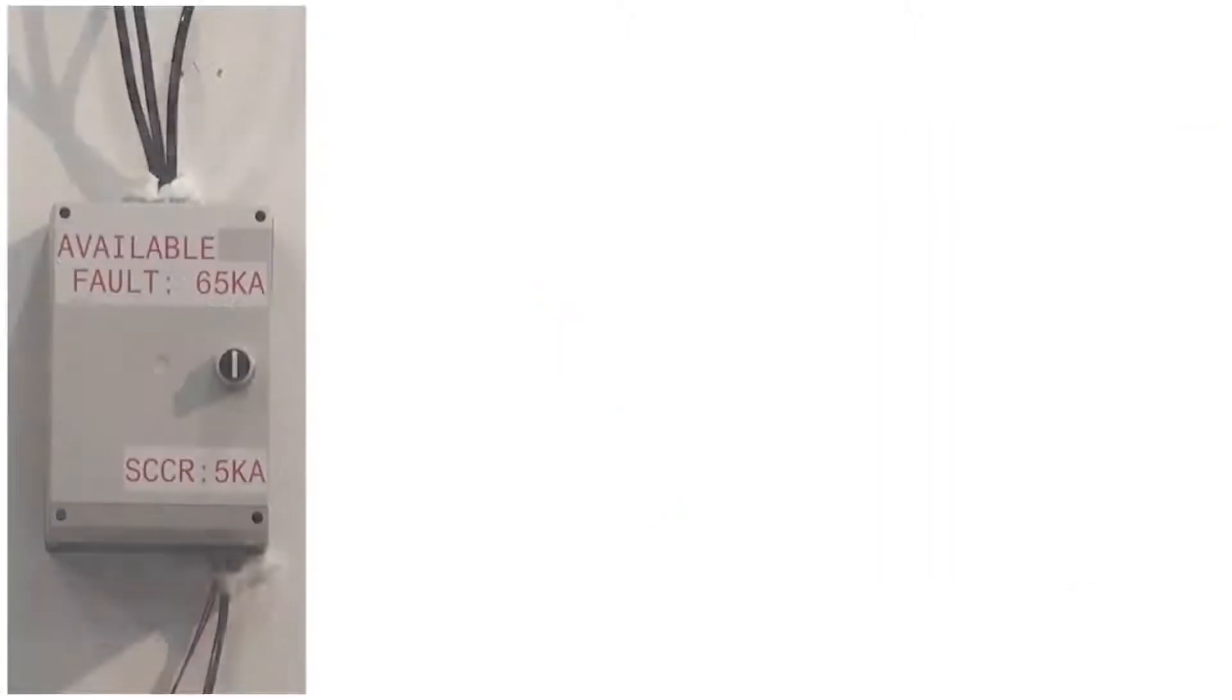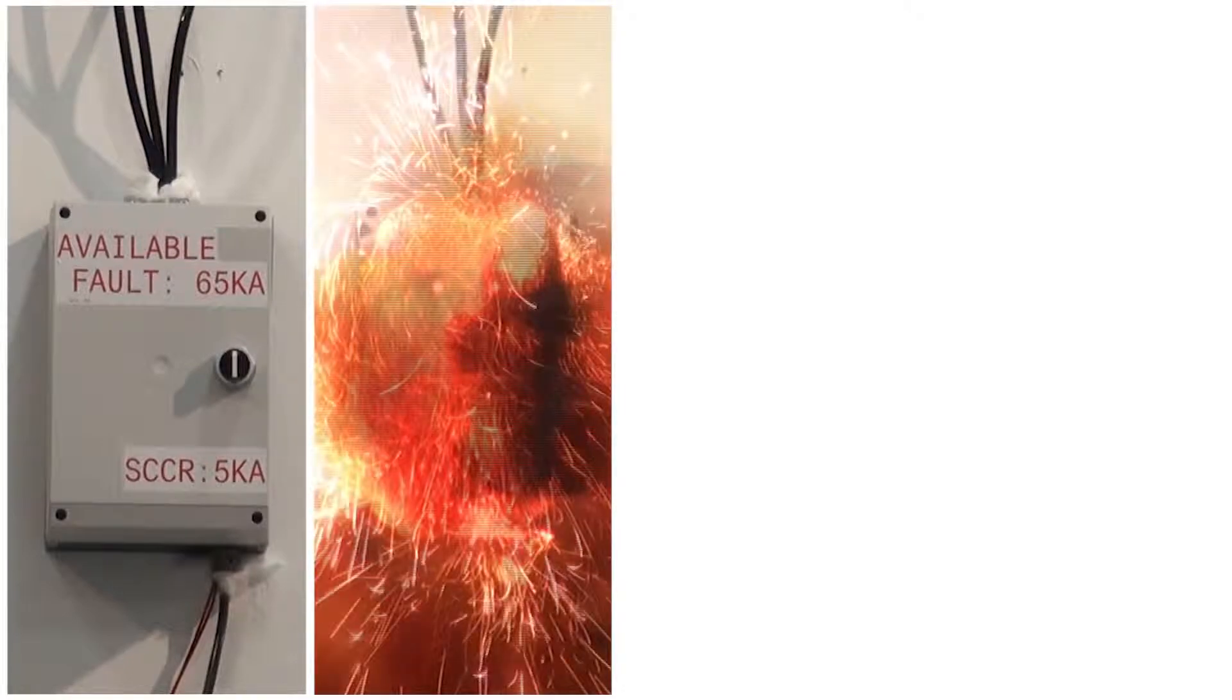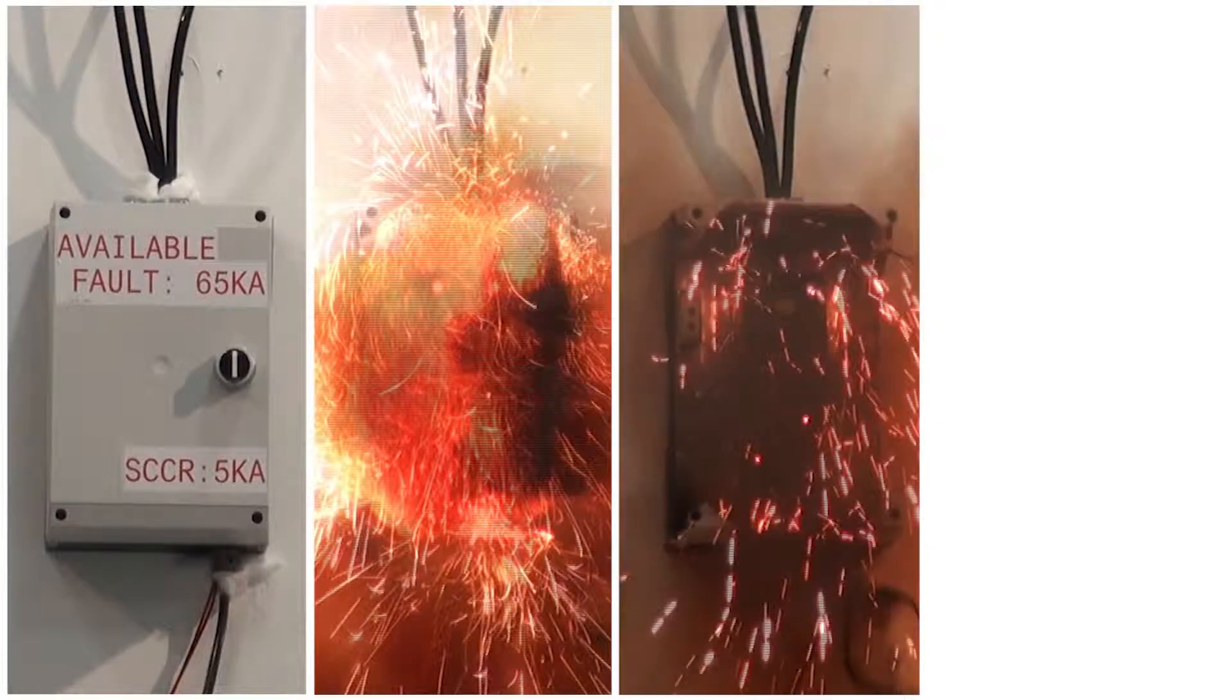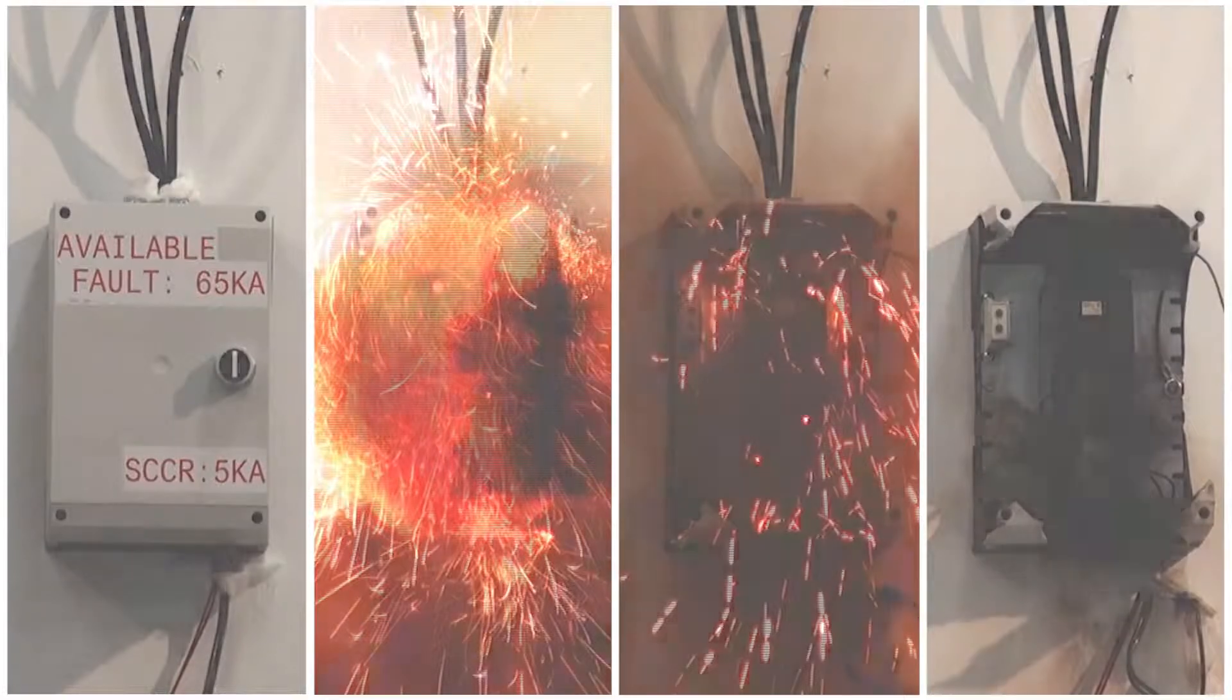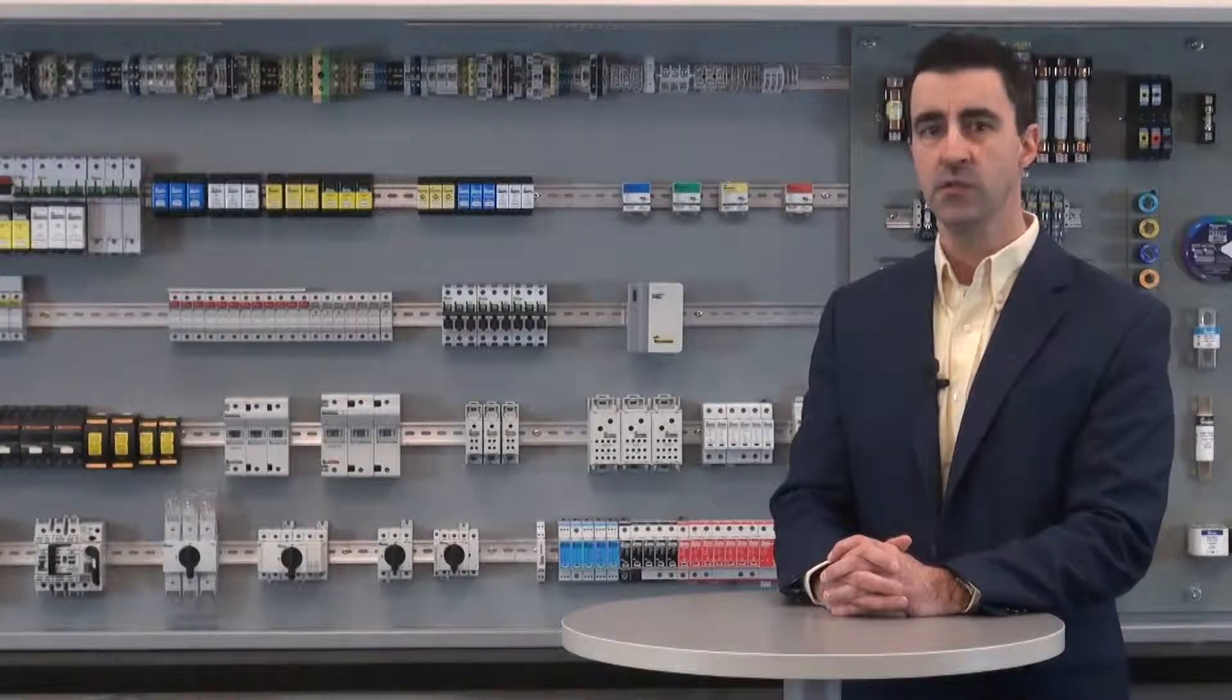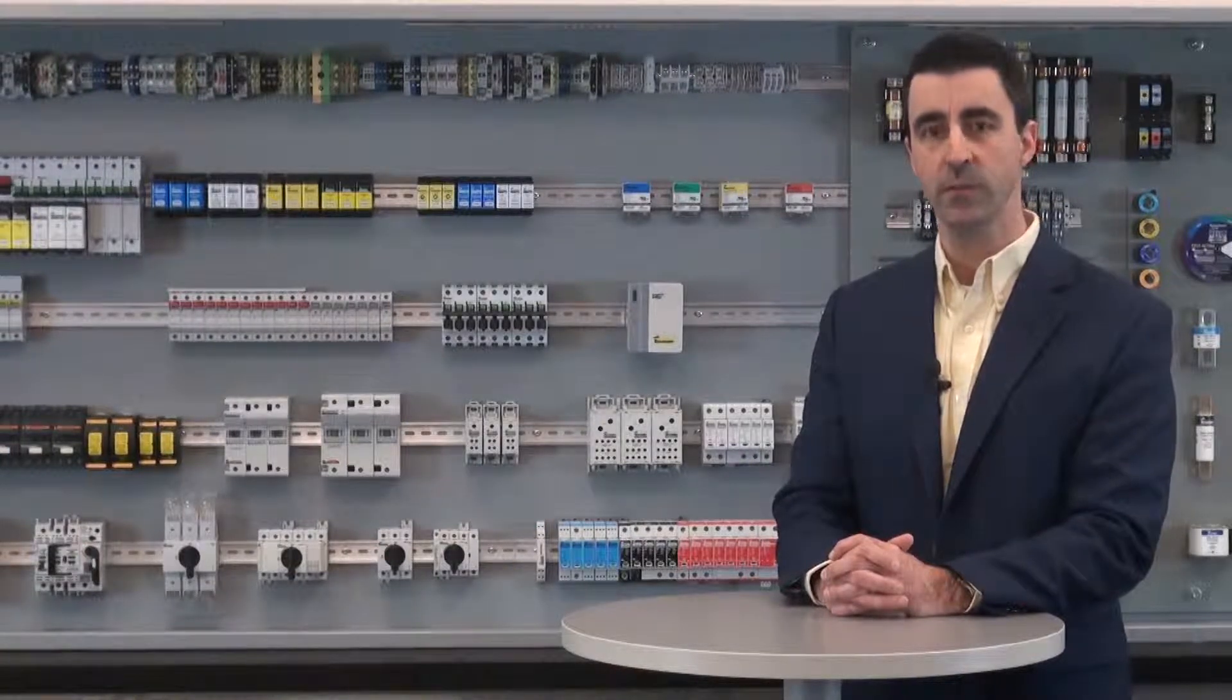At the same time, huge magnetic forces developed between conductors can crack insulators and destroy bracing structures, with the maximum mechanical force exerted being proportional to the square of the instantaneous peak current. It is extremely important that overcurrent protective devices limit fault currents before they reach their full potential.